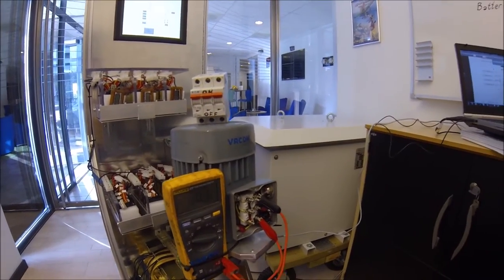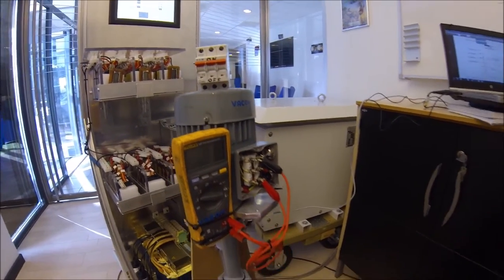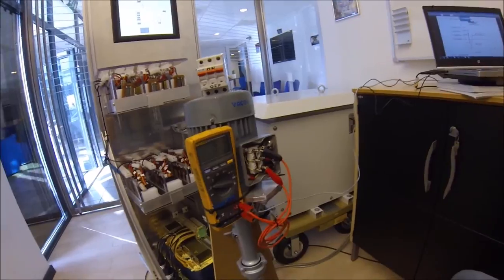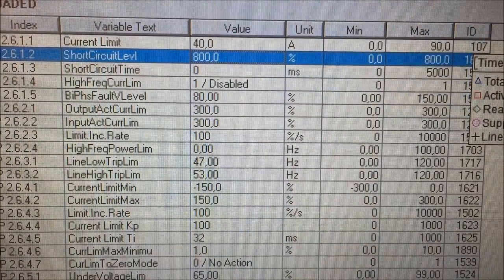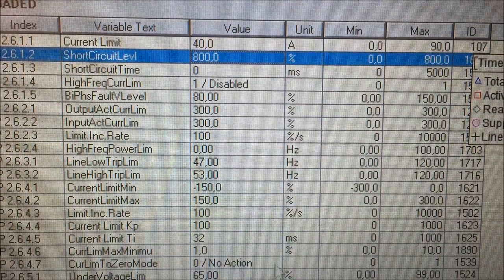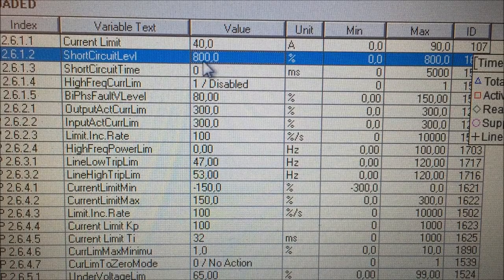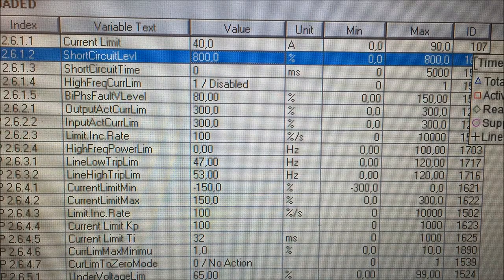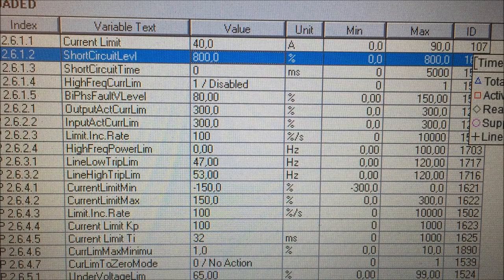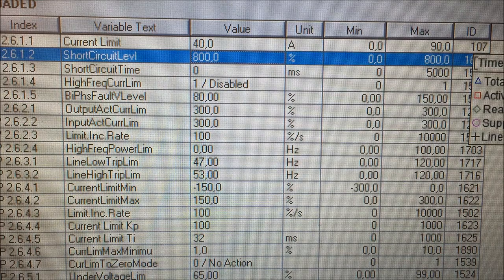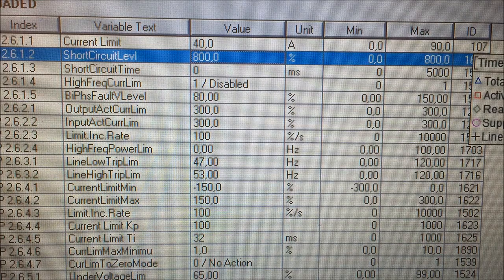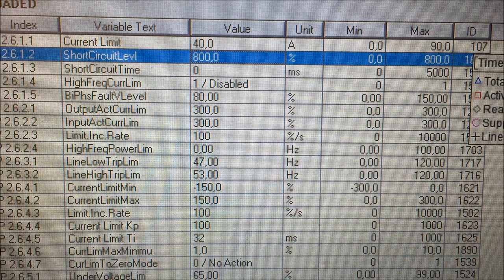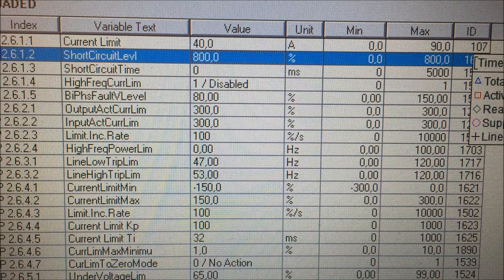Now we have the short circuit current limiter disabled by writing 800 here. Let's see how the system reacts. It will probably be tripping with a fault F1 over current and not blowing any fuses. It will just trip.